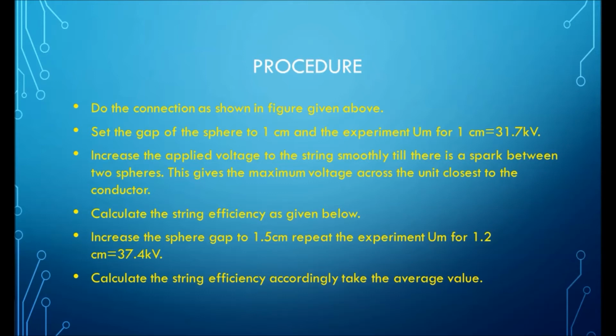This is the procedure. First check the circuit according to the circuit diagram, as already mentioned here. First set 1 cm, then the voltage is 31.7 kV. This is the flashover voltage of the sphere gap. If you set the sphere gap at 1 cm, then the flashover voltage is 31.7 kV. This is the actual condition, not atmospheric condition, but I have calculated it for atmospheric condition. Then you can change the sphere gap distance to 1.2 cm, then the flashover voltage is 37.4 kV. 31.7 is a peak value and 37.4 is also a peak value.